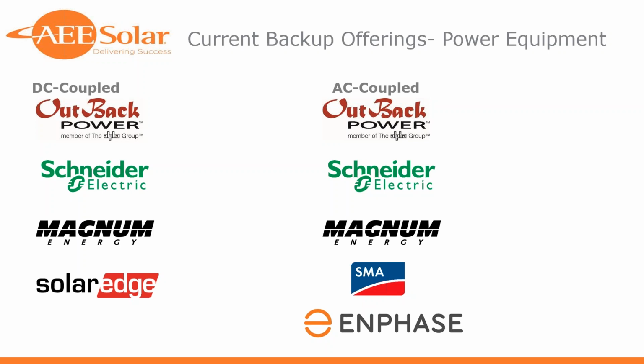I'd say if you're looking for more flexibility on sizing, sometimes you need a smaller system, sometimes you need a larger system, you're going to be looking at one of the top 3 companies there on the left. Some limitations on the SolarEdge product. You are a little bit headroom constrained on supporting backup loads. There's just not a lot of headroom between the continuous output rating and the max surge rating on the SolarEdge plus LG Chem solution. Also no 3-phase options, no generator interconnect. Really just depends on how many options and features you want in the system.